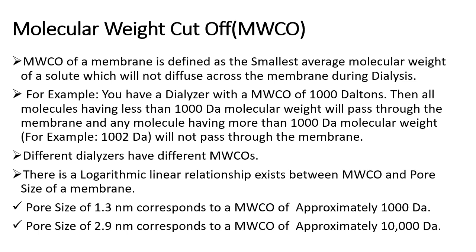Different dialyzers have different molecular weight cutoffs. There is a logarithmic-linear relationship between molecular weight cutoff and pore size of a membrane. For example, a membrane with a pore size of 1.3 nanometers has an approximate MWCO of 1000 daltons, while a membrane with a pore size of 2.9 nanometers has an MWCO of approximately 10,000 daltons.